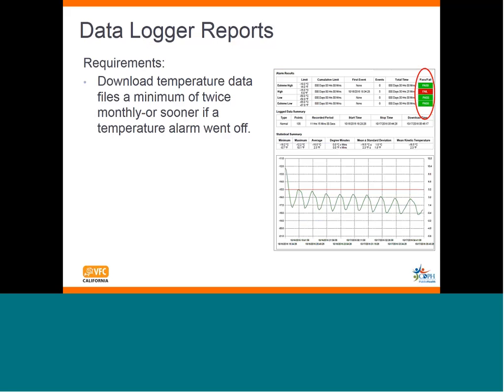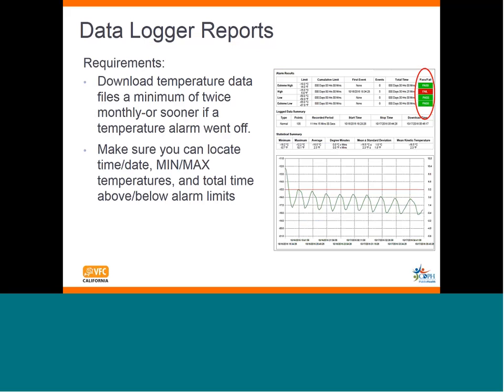Download temperature data files a minimum of twice a month, or sooner if a temperature alarm went off. Make sure you can locate the time, date, minimum and maximum temperatures, and the total time temperatures were out of range, either above or below the alarm limits. Review every time an alarm goes off before you report the excursion, and learn how to analyze and review for any out-of-range temperatures.